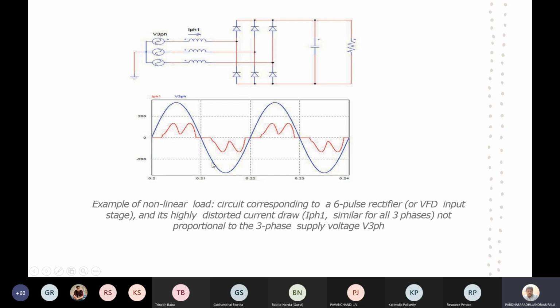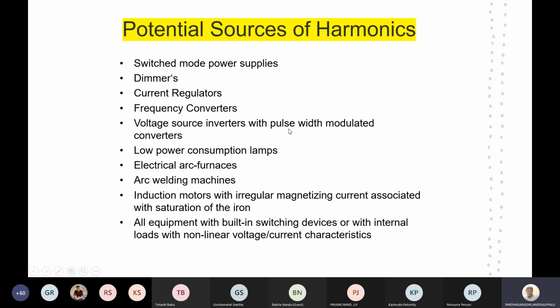What you can say is we supplied a 50 hertz signal here, but the output is not a 50 hertz signal. So the result of these harmonics is that the supply will again be impacted. This will again be a source of distortion to the supply. We already discussed the potential sources: switched mode power supplies, dimmers, current regulators, frequency converters, voltage source inverters with pulse width modulated converters, low power consumption lamps, electrical arc furnaces, arc welding, and magnetizing current associated with saturation of the iron. All equipment with built-in switching devices, or with internal loads with nonlinear voltage-current characteristics, are the main sources of harmonics.